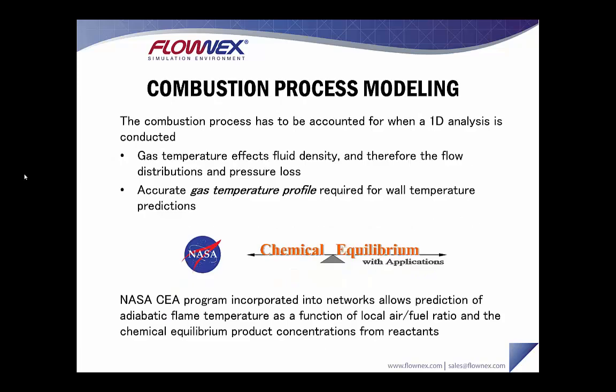The combustion process is also very important to take into account. Gas temperature affects fluid density and therefore the flow distribution and pressure loss through your network. An accurate gas temperature profile is required to calculate wall temperatures. Within Flownex there is a NASA CEA program that can be incorporated into networks and allows the prediction of an adiabatic flame temperature as a function of local air-fuel ratio, and it will also calculate the chemical equilibrium product concentrations from reactants.